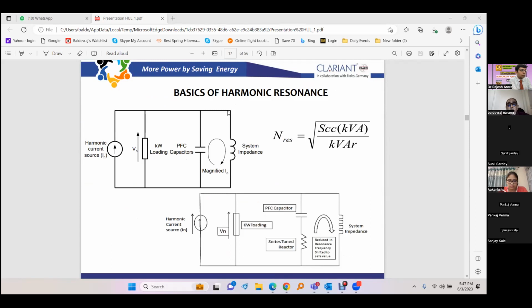So this is a transformer. We are representing the transformer and the system beyond that as a system reactor. And we have a load connected in parallel to that. And this load is non-linear. So we are representing a harmonic current source like this. And then we have power factor improvement capacitors also connected in parallel. So these harmonic currents, which are there because of the non-linear load, flow through the capacitors and they flow through the system also, and they get exported to the grid, where they get converted into voltage disturbance, voltage harmonics, and they come back to everybody.